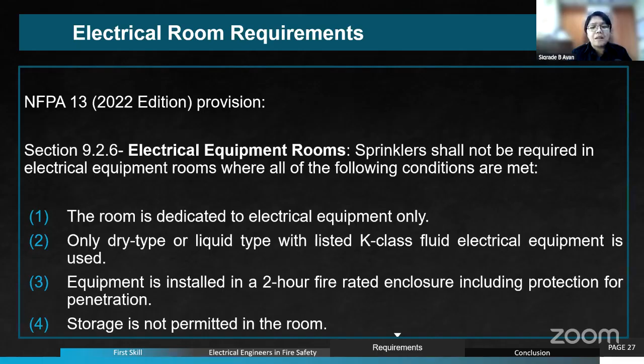sprinkler systems or sprinklers are not required in the electrical equipment rooms provided that these four conditions are met. Una, the room is dedicated to electrical equipment only. Pangalawa, only dry type or liquid type with listed K-class fluid electrical equipment is used. And number 3, equipment is installed in a 2-hour fire-rated enclosure, including protection for penetration, and storage is not permitted in the room.